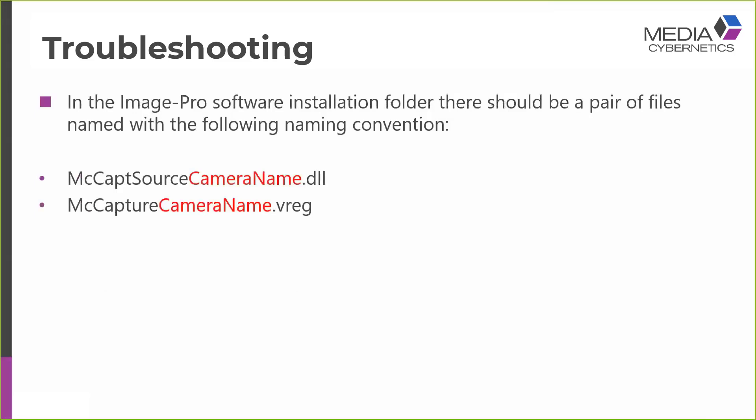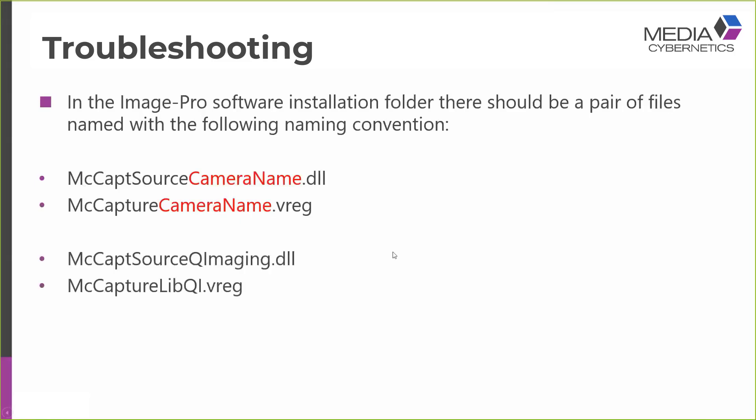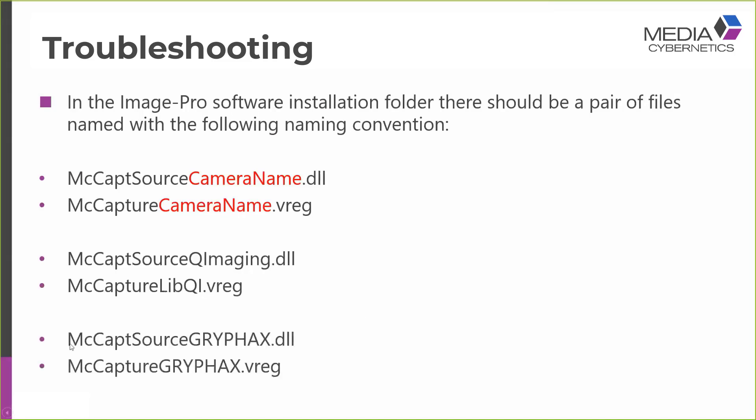The next thing to check is that the Image Pro software installation folder, there should be a pair of files named with the following naming convention. And these are the files that are installed by the Capture interface. So they should be named MCCaptSource, then the camera name, and then the suffix DLL. And there should be a partner file named MCCapture with the camera name and then the suffix .vreg. So examples of real names that you should find are things like MCCaptSource QImaging DLL and its partner MCCapture QImaging.vreg. And here we have another pair, MCCaptSource Gryphax.dll. So these were the ones that are installed for the camera I'm working with, the Jenoptik Gryphax. And there's its partner file, MCCapture Gryphax.vreg.